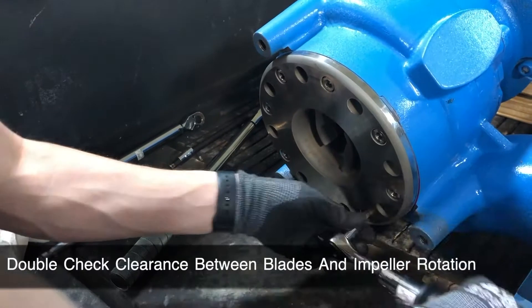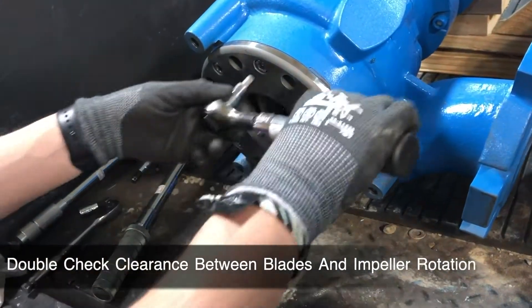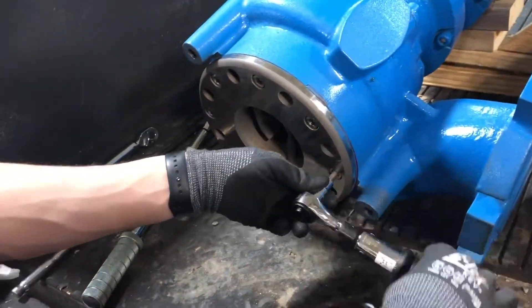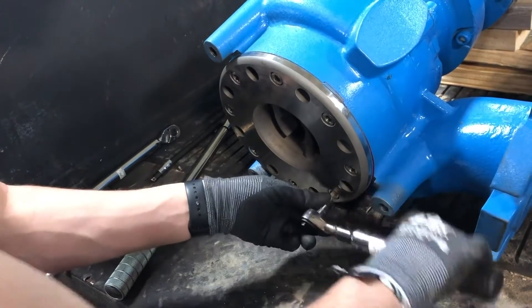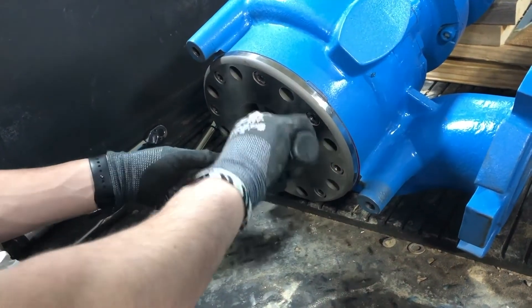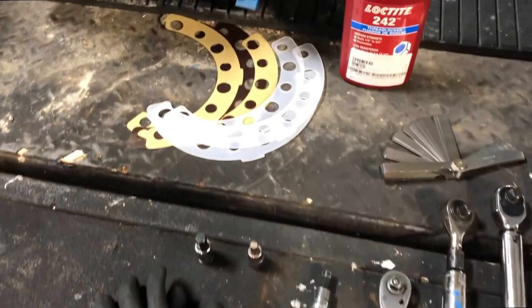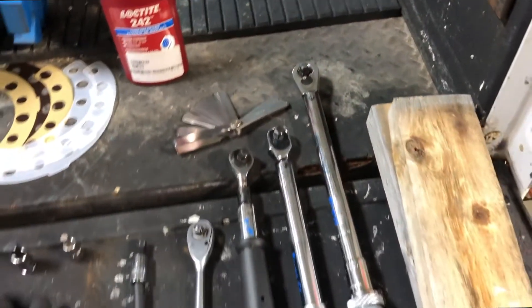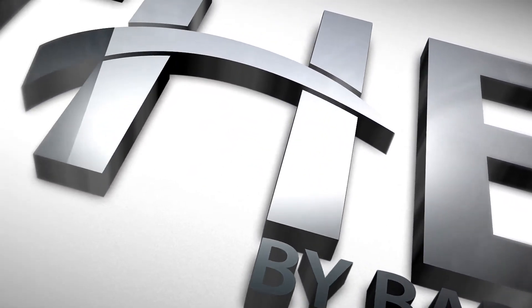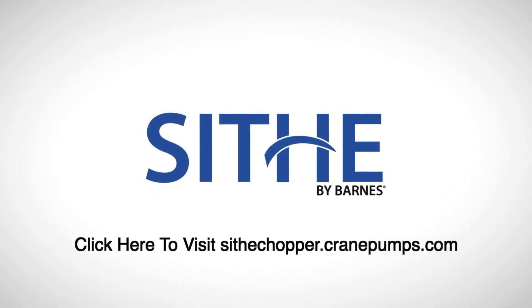Once all bolts have been tightened, double-check the clearance between the blades and check again that your impeller spins. With just a few tools, a hoist, and a chuck bed, you can easily service, repair, or upgrade a Sithe chopper pump. This ease of serviceability is just one of the many benefits of the Sithe chopper portfolio by Barnes. To learn more about the Sithe chopper, visit sithechopper.cranepumps.com.